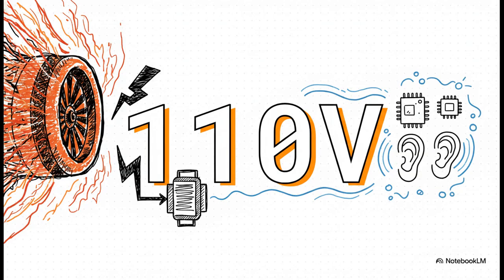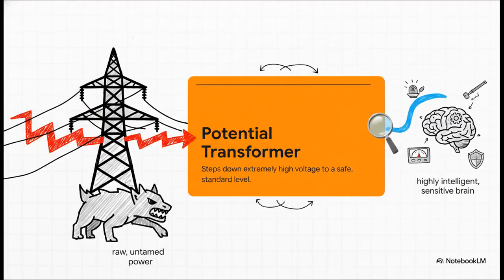So we have to take that roaring 132 kilovolt jet engine and somehow turn it into a manageable whisper, specifically a perfectly scaled down whisper of exactly 110 volts. By forcing that extreme high voltage to essentially speak softly, our sensitive electronics can safely listen to what the grid is doing. They can measure it accurately and protect the whole system without getting completely destroyed in the process. And enter our hero, the potential transformer.